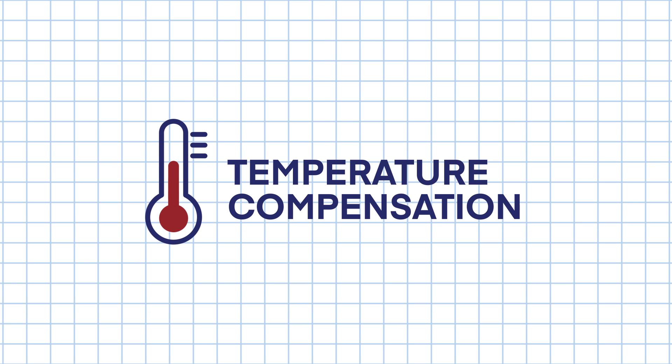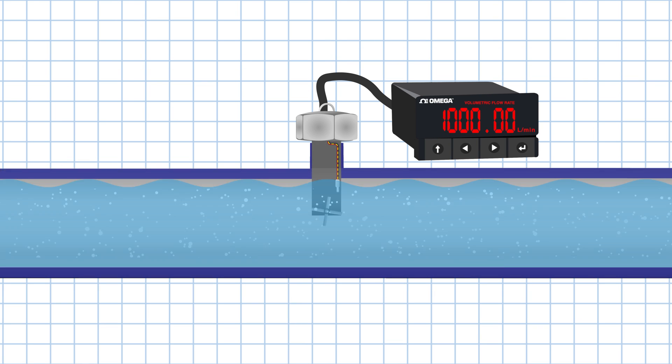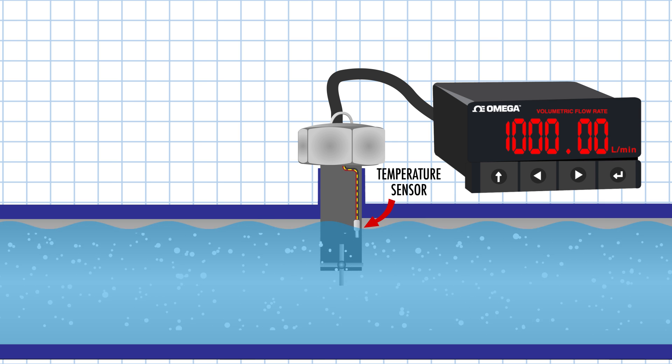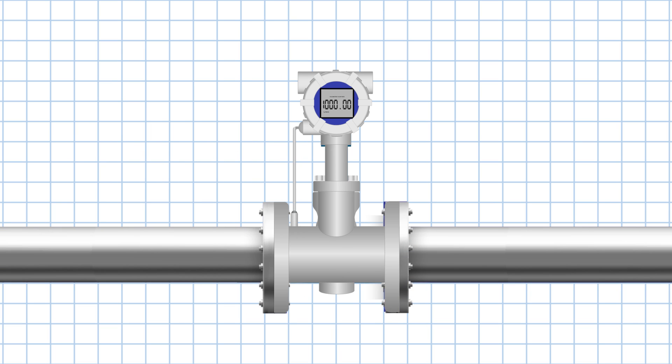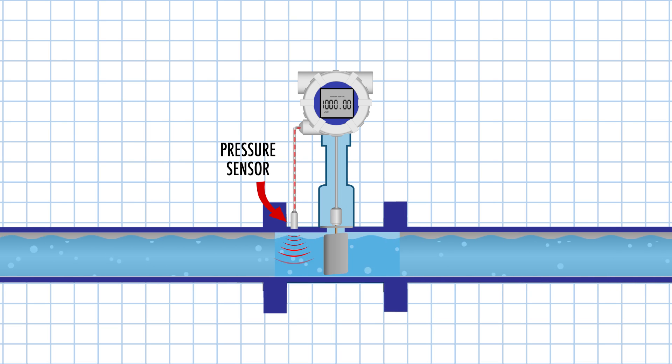Temperature compensation can often be achieved with a temperature sensor built into the flow meter, so it can use the temperature information to calculate the corrected volumetric flow rate, based on the known relationship between temperature, density, and volume. Pressure changes can affect the density of a substance as well. That's why volumetric flow meters can be equipped with pressure sensors, so that the flow meter can apply correction factors or algorithms that take into account the pressure's impact on the substance's density, and calculate the corrected volume flow rate accordingly.